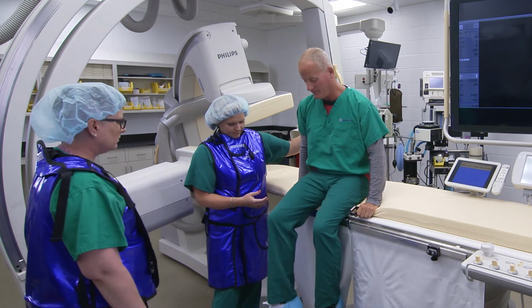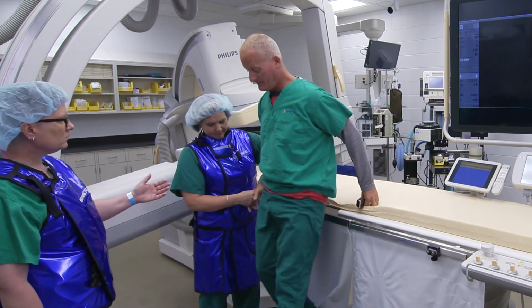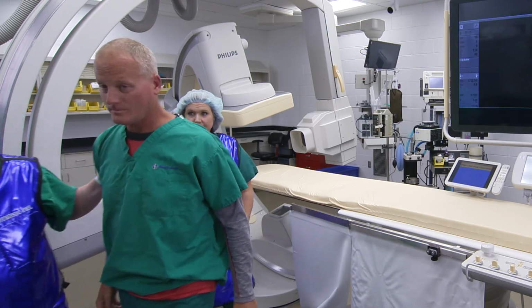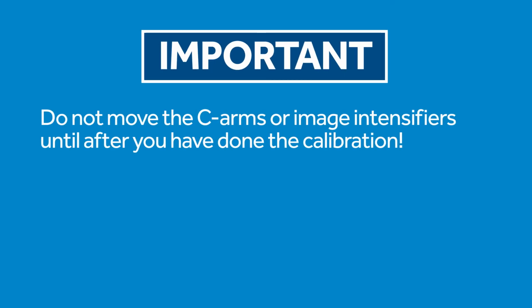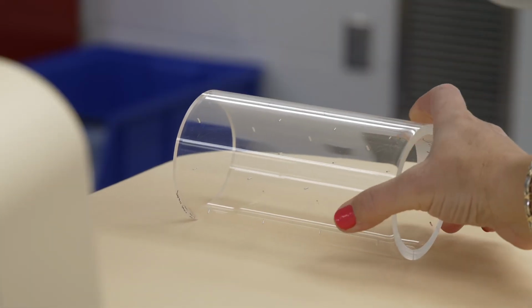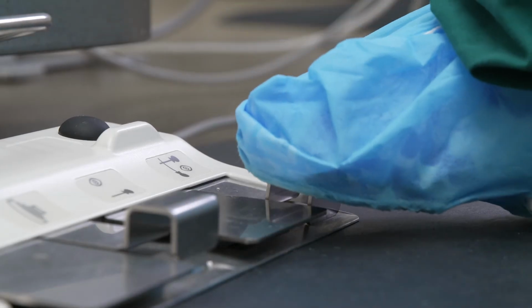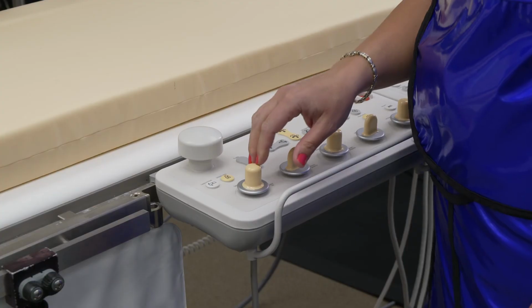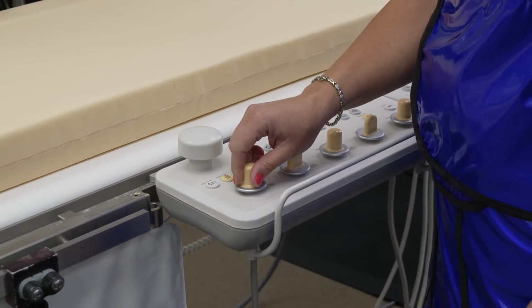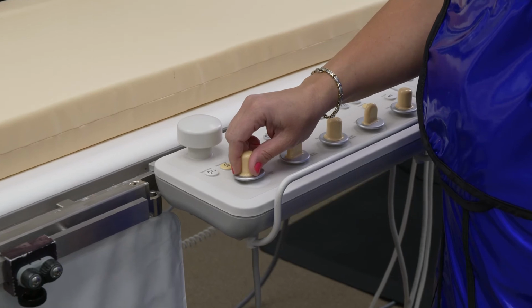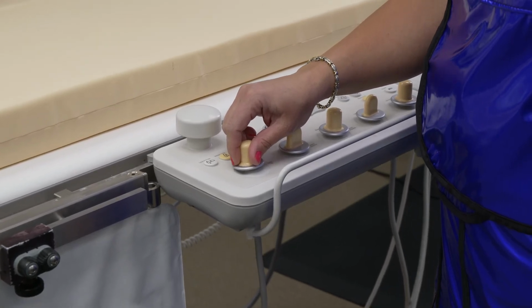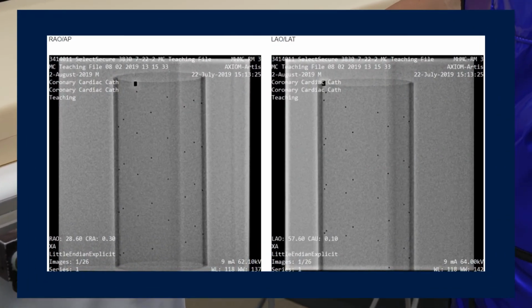After all 3 data acquisitions are done, have the patient carefully get off the table and exit the room. Do not move the image intensifiers or the position of the C-arms. Put the calibration object on the table on its side with the larger BB facing upwards. You can translate the table only to get the phantom into the field of view. Limit moving the table up and down, as this may automatically move the image intensifiers. If this happens, the image data is not usable.